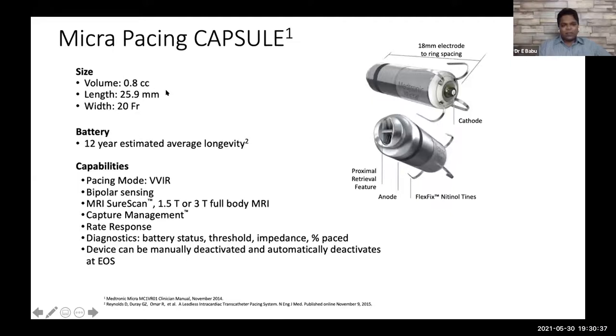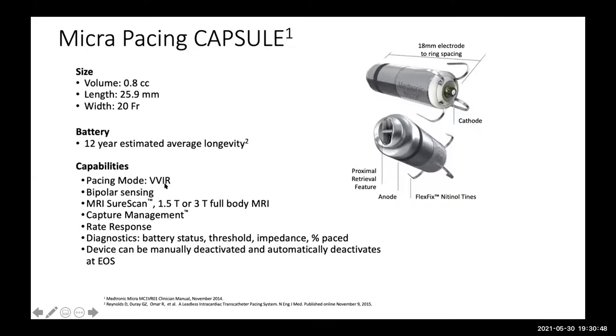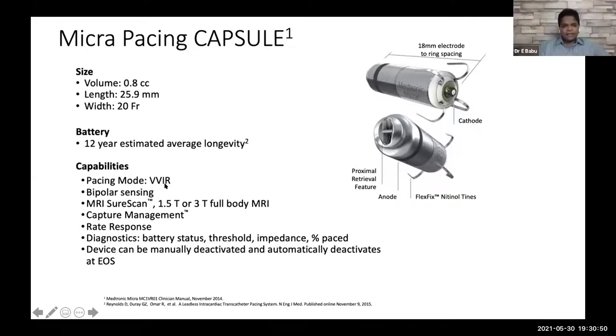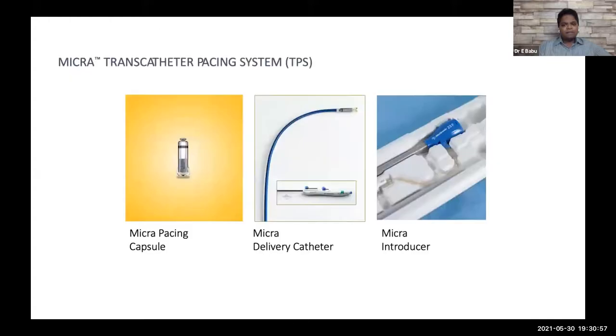As I said, the volume is less than 1 cc, it's only 0.8 cc and around 25 mm in length. Longevity is good, and it's MRI compatible, both 1.5 and 3 Tesla. The mode with the Micra is currently VVIR, that is, sensors in the ventricle, pacing in the ventricle. So it's only a single chamber currently.